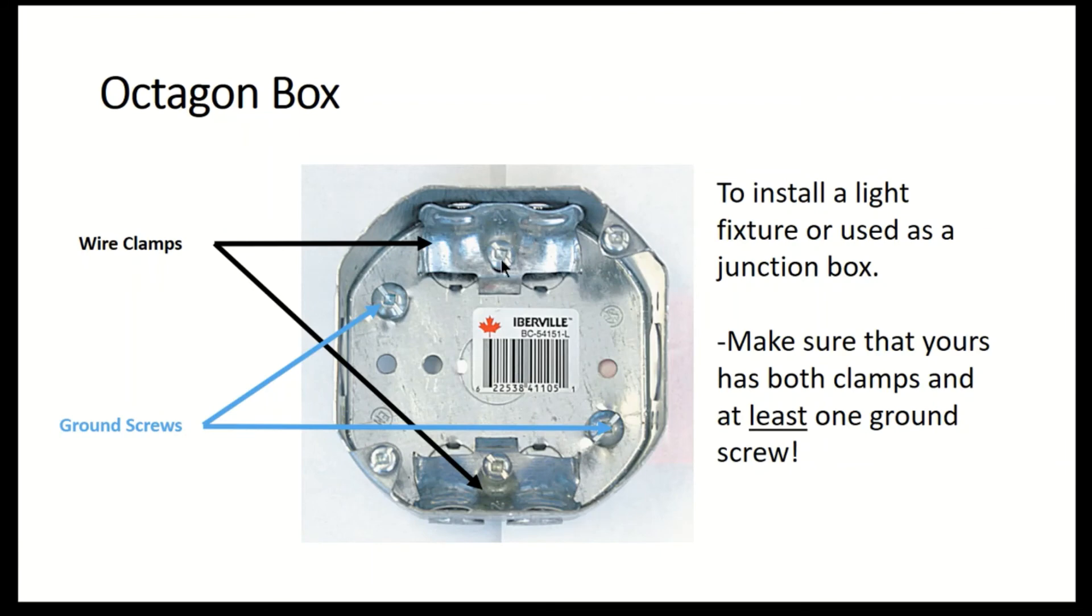Here's the anatomy of the octagon box. You'll see that we have two wire clamps. The wires will come underneath there and then we'll tighten this screw and that provides strain relief. So if the wires are ever tugged they'll never pull out of what we're attached to. We also have two ground screws that come standard on these octagon boxes. One of the ground wires will need to be attached to there. That's making sure that we follow the bonding rules outlined in the Canadian electrical code.